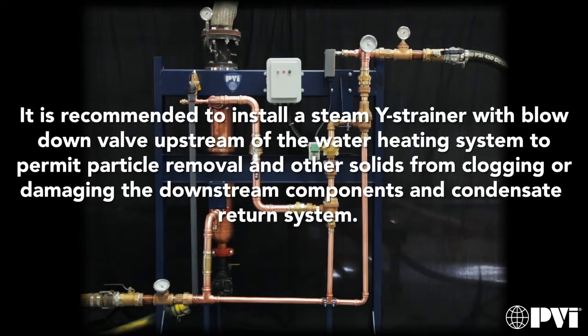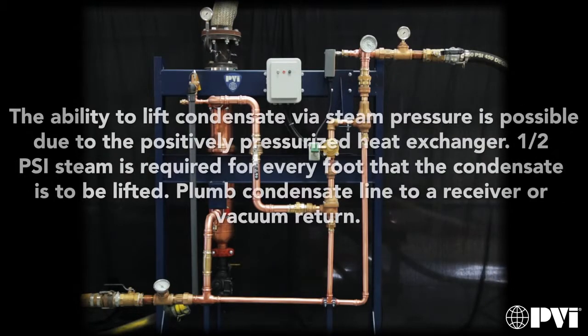It is recommended to install a steam Y strainer with blowdown valve upstream of the water heating system to remove particles and help prevent clogging or damaging the downstream components and condensate return system. The ability to lift condensate via steam pressure is possible due to the positively pressurized heat exchanger. 1/2 psi steam pressure is required for every foot that the condensate is to be lifted. Plumb the condensate line to a condensate receiver or vacuum return.